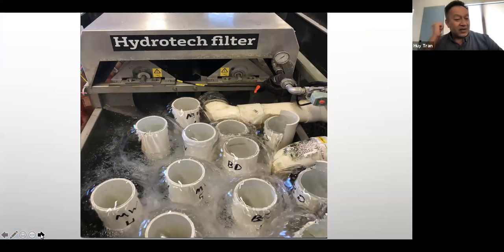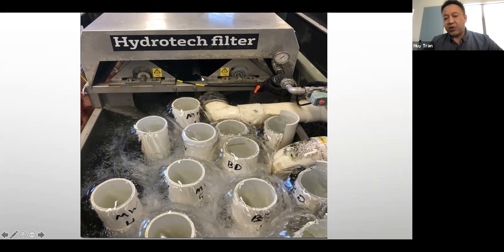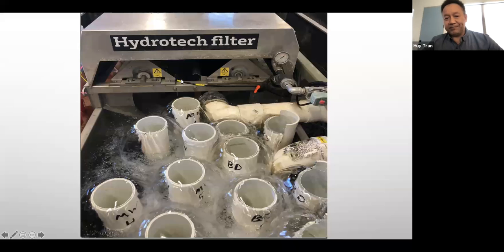Some really terrible design — if you look at this pipe, it's not supported except for small pieces of plastic under this cradle. These small mistakes add up significantly. That's a 36-inch diameter pipe — a lot of weight on that little point loading. Here's another system: there are actually 14 overflow drains all going into a common drum filter. Originally they didn't even have labels so they didn't know which drain was which. Proper design will save you all kinds of headache and mortality.